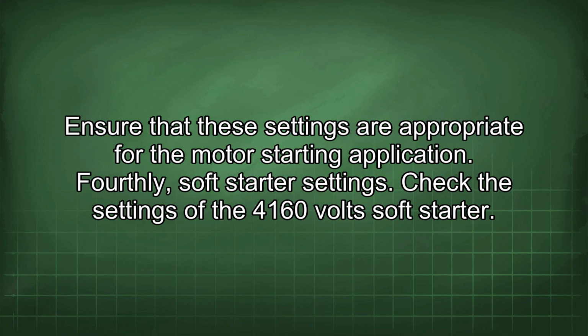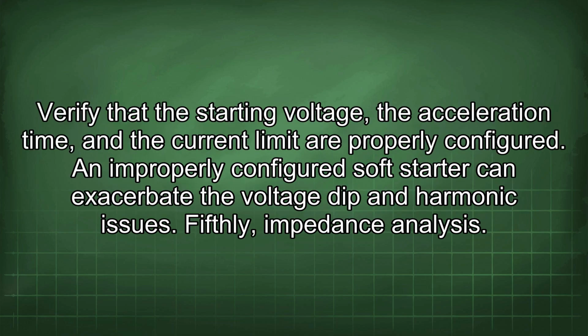Fourthly, soft starter settings. Check the settings of the 4160 volt soft starter. Verify that the starting voltage, the acceleration time, and the current limit are properly configured. An improperly configured soft starter can exacerbate the voltage dip and harmonic issues.